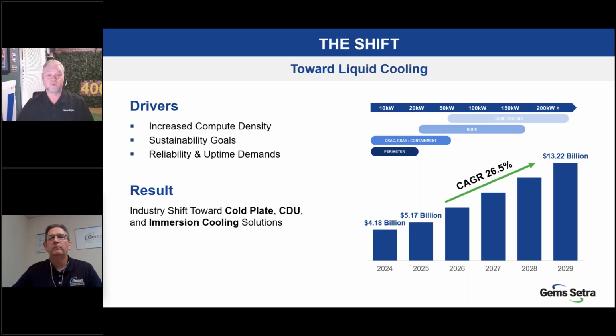Once upon a time, rack densities were far more manageable, generating 10 to 20 kilowatts of power or less. And for these applications, traditional air-cooled methods were okay. As those densities rose, and they continue to rise, cooling methods need to change. You see the chart on the upper right corner, where with the lowest densities, perimeter cooling is adequate. In your office when you have your server room, there's just a standard air conditioner to cool that space. Once that isn't sufficient, then special air cooling equipment like CRAC or CRAH and hot or cold aisle containment strategies are more suited. As things get hotter, technologies like rear door heat exchangers or other hybrid cooling methods come into play.